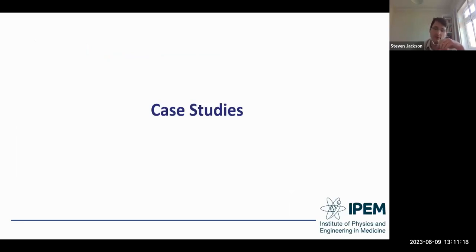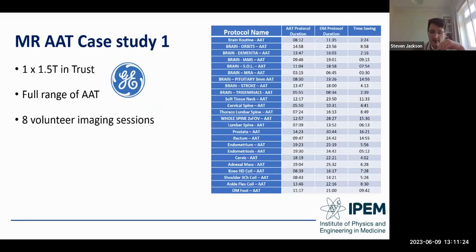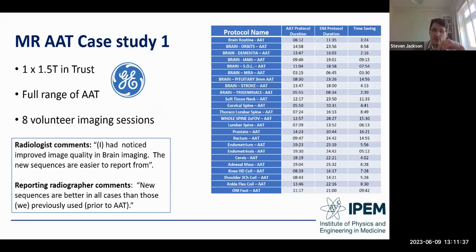Case studies from the North West: first, a trust with a 1.5 Tesla GE scanner with the full range of AAT software. Over 8 volunteer imaging sessions, protocol timings were significantly reduced. Comments from end users: radiologists noted improved image quality in brain imaging and found new sequences easier to report from. A reporting radiographer said the new sequences are better in all cases than those previously used prior to AAT — a very encouraging endorsement of the AI technology on the GE system.